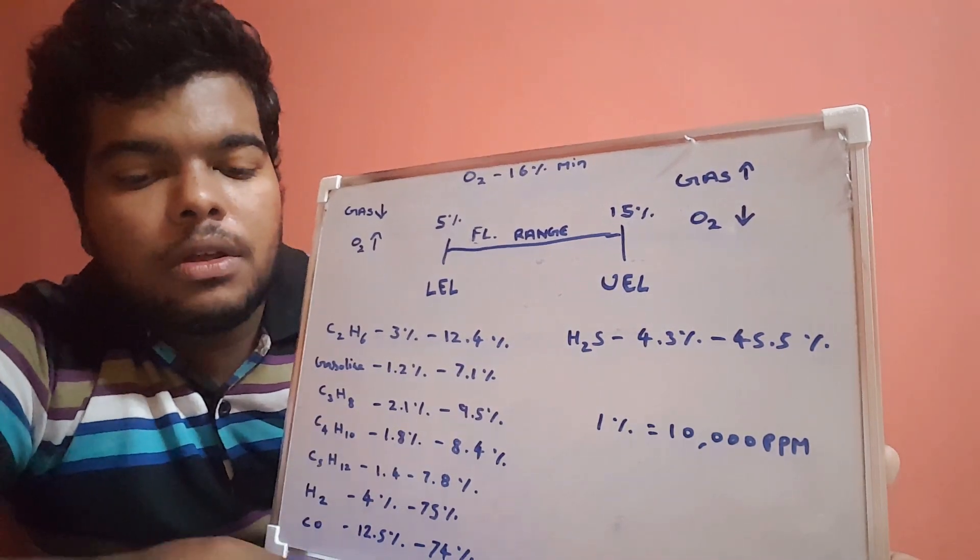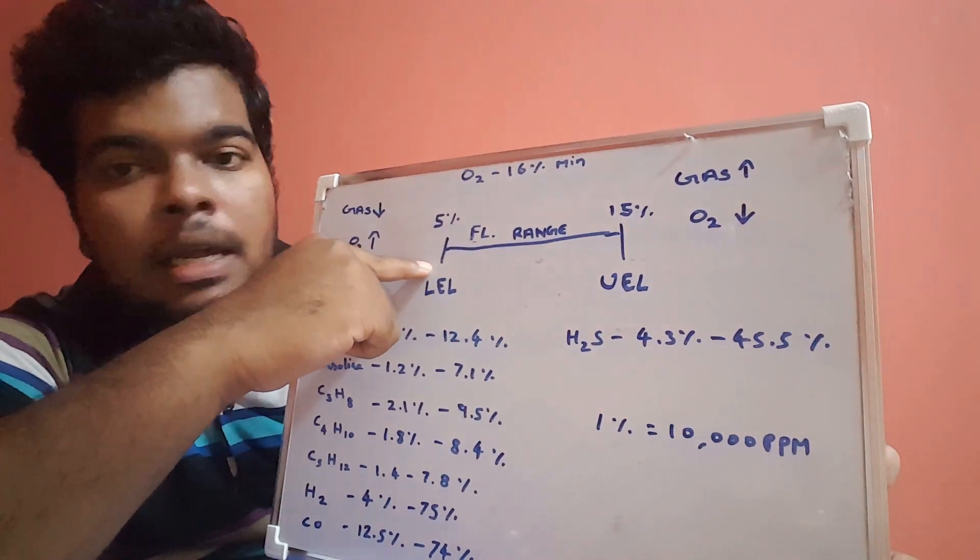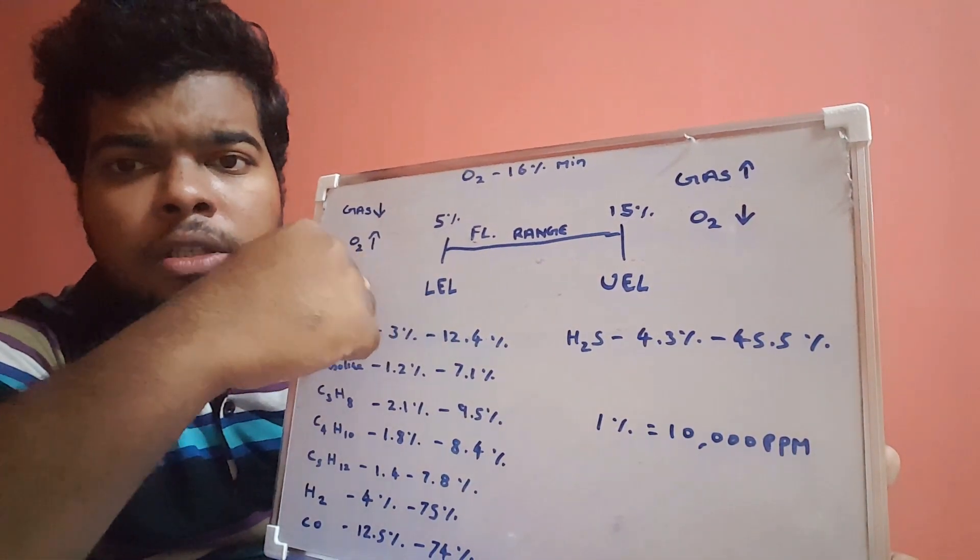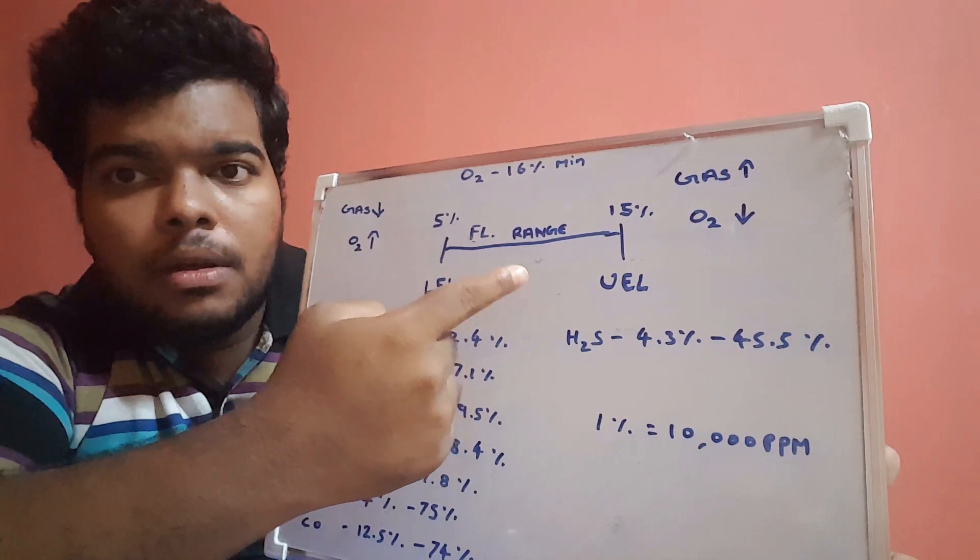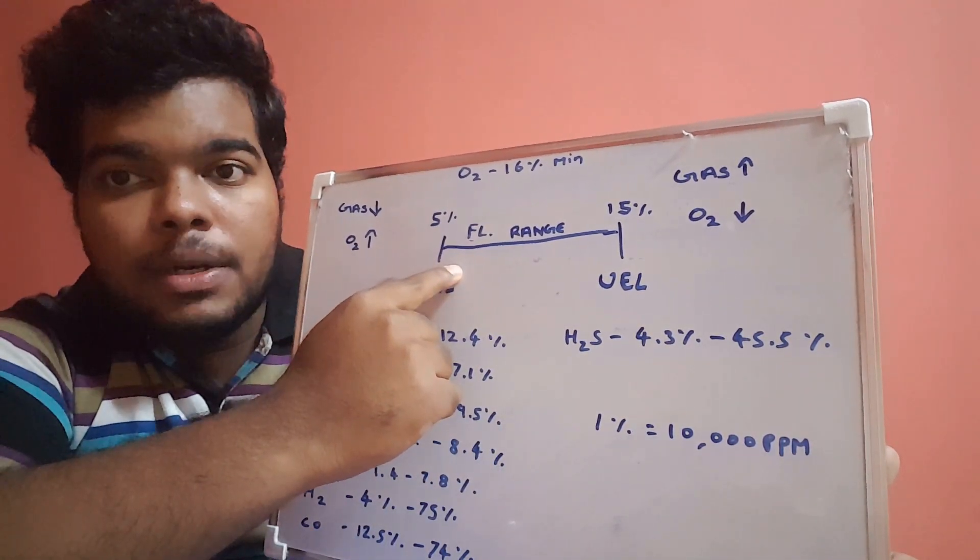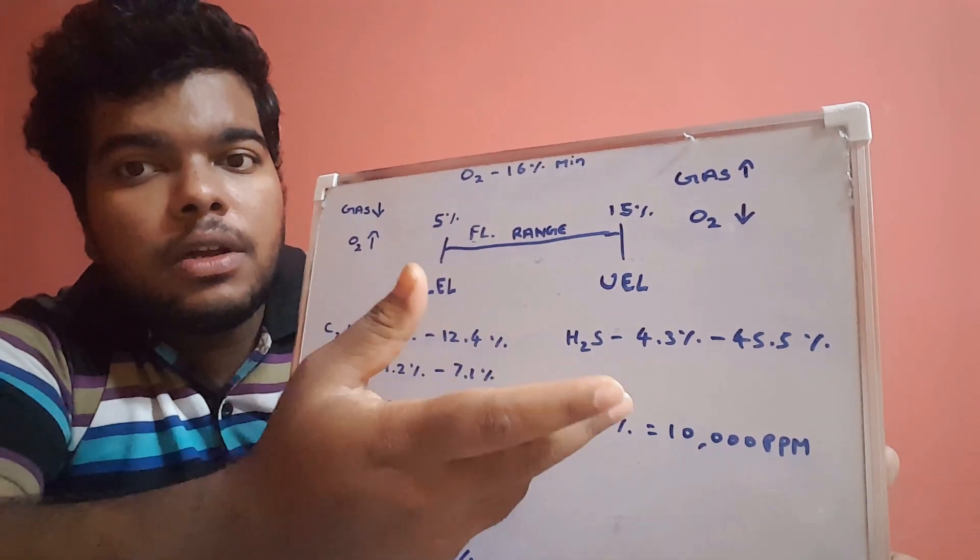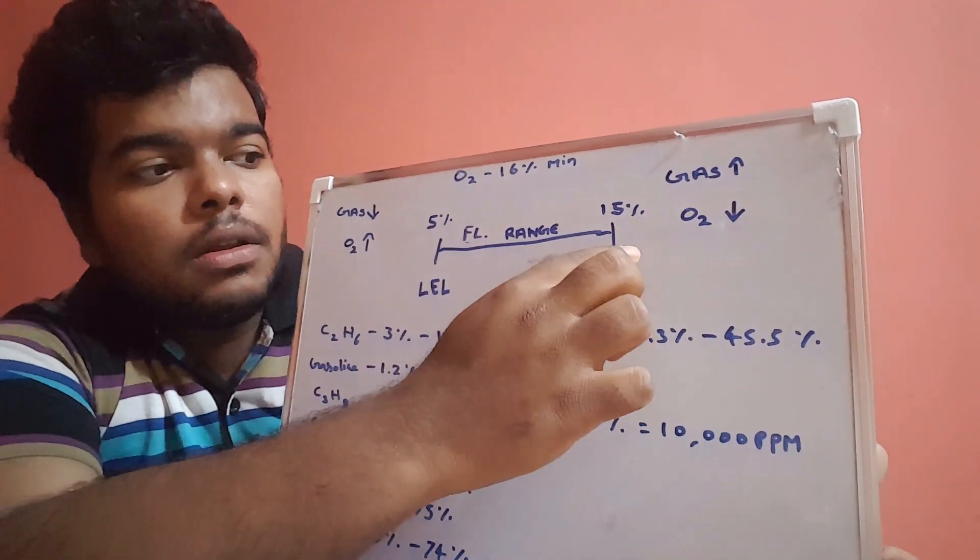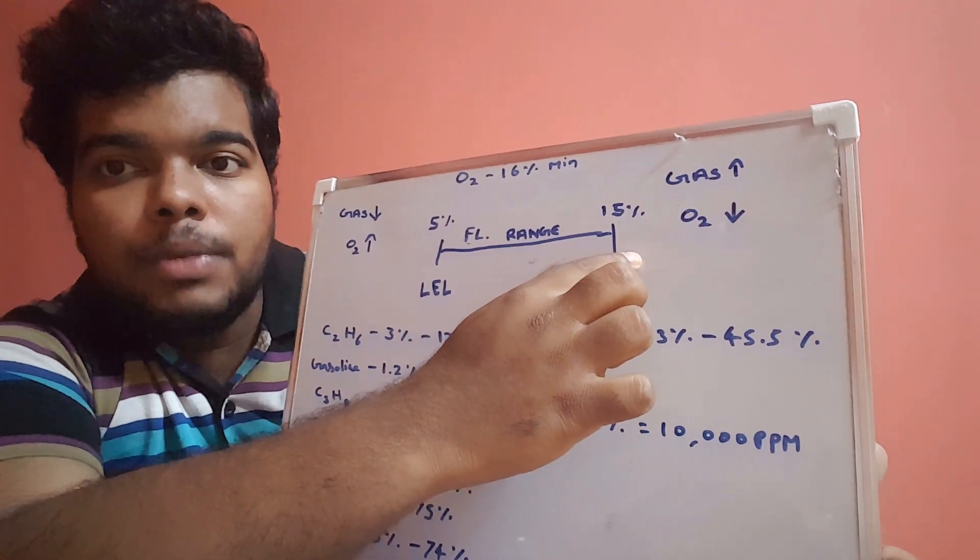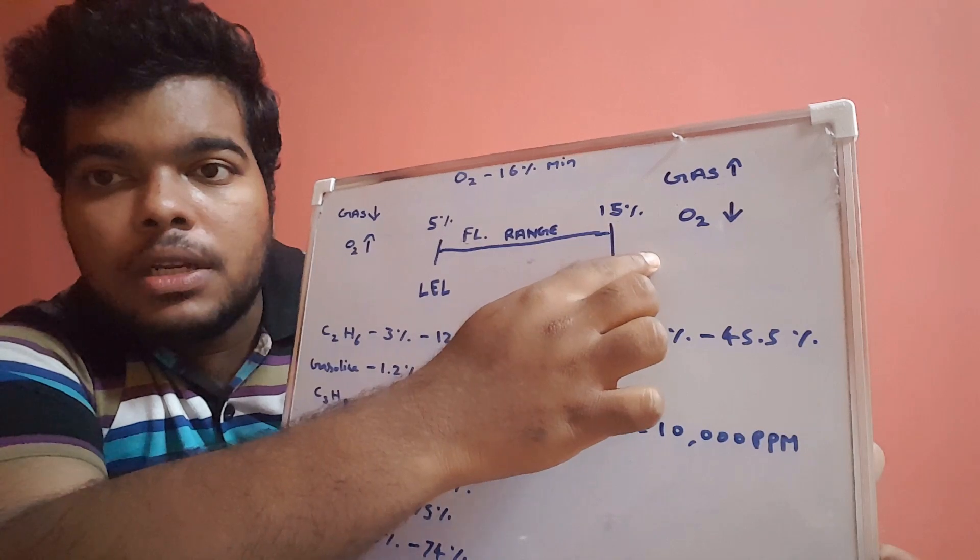When it comes to LEL values, it will detect from 0 up to 15, but the alarm will not be on until it reaches 5 percentage. When it reaches 5 percentage, the alarm will turn on. When it goes beyond 16 and 17 percentage, I mean above 15 percentage, definitely the oxygen level will go down first.